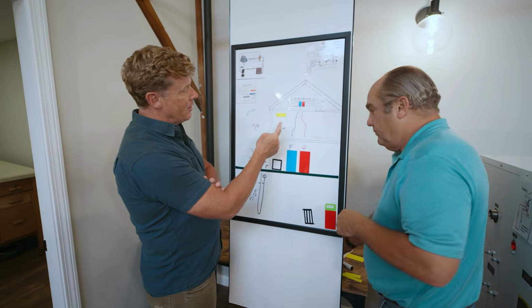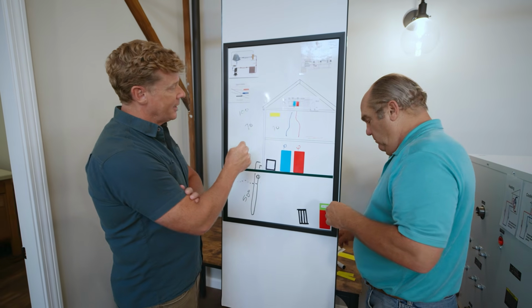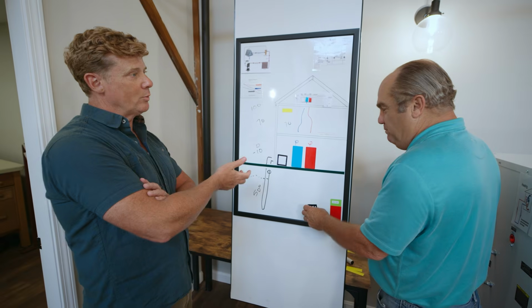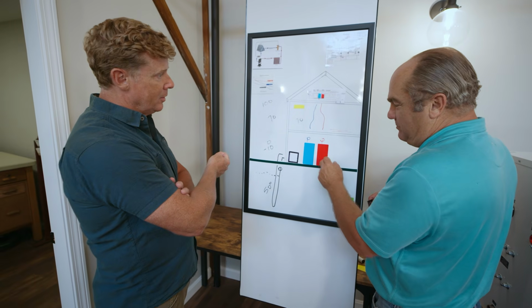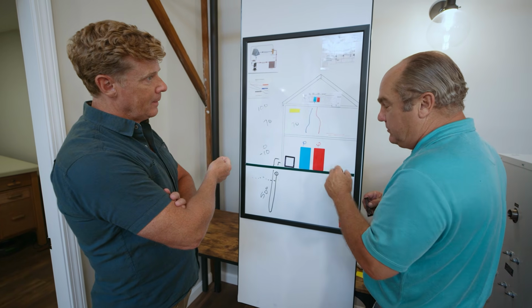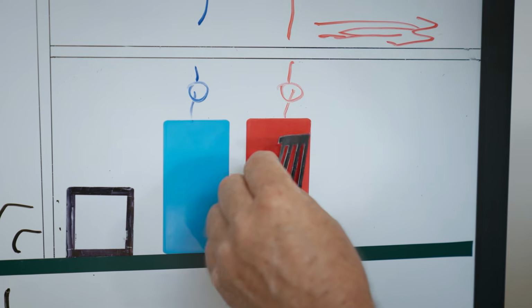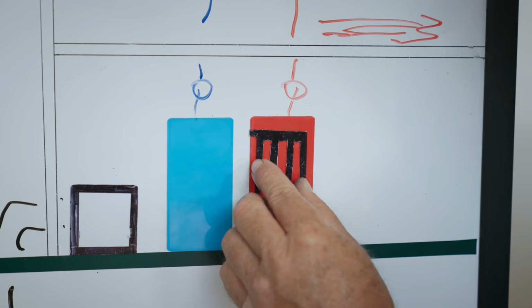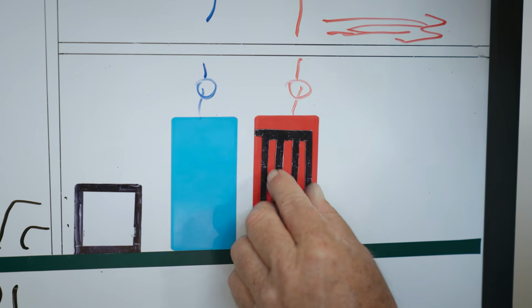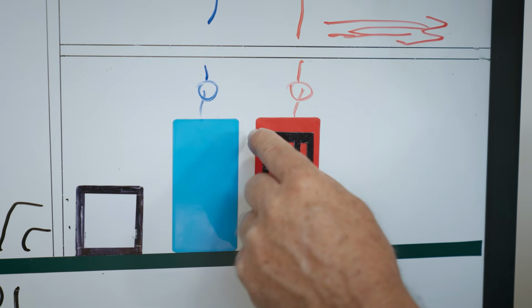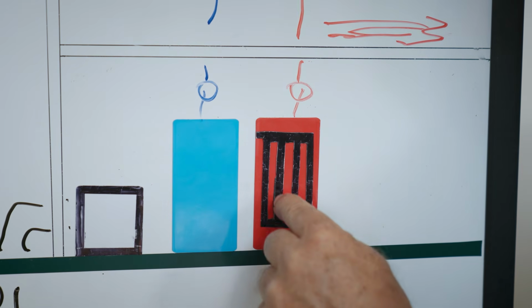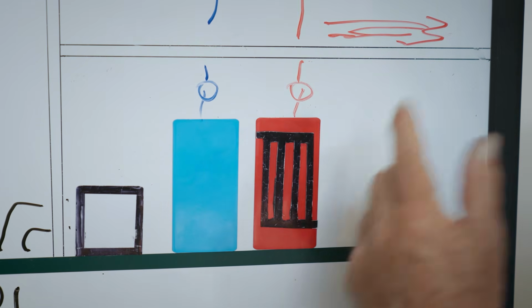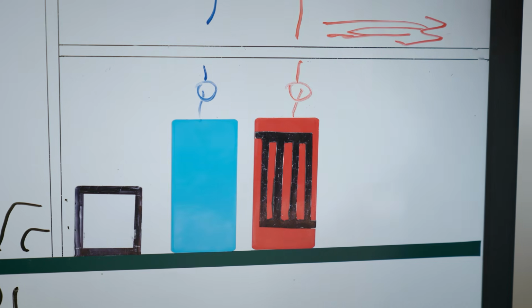So now you've made the house comfortable. Yep. Thank you for that. I still want to take a shower or run the dishwasher. Where do I get my hot water from? Well, this beautiful buffer tank, the storage tank storing BTUs, we've ordered it with a heat exchanger inside it, so that we're going to take some heat off of the heat pump through this coil. Potable water will come through here, and now that's going to be hot enough to make the faucets hot enough.